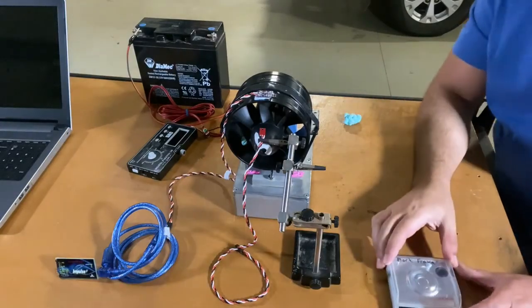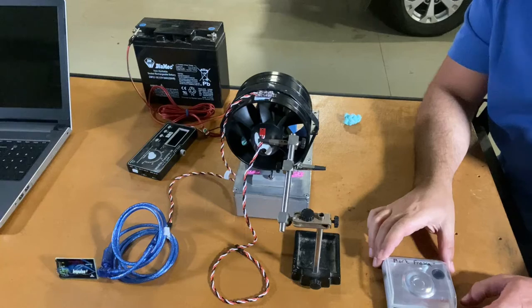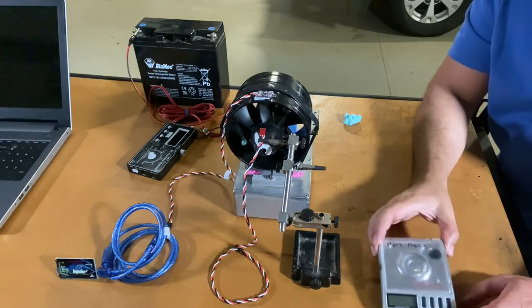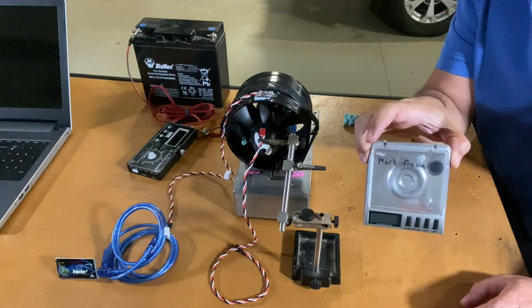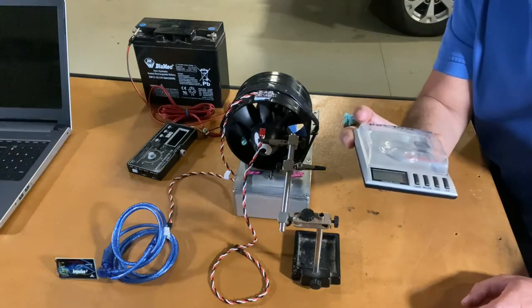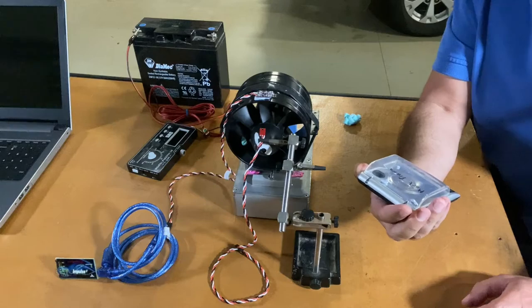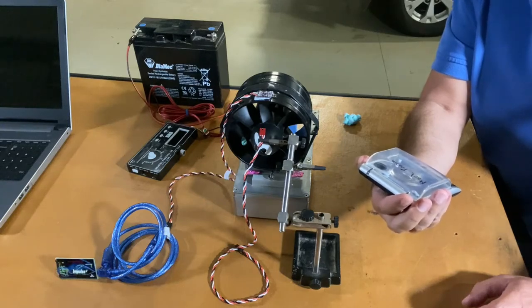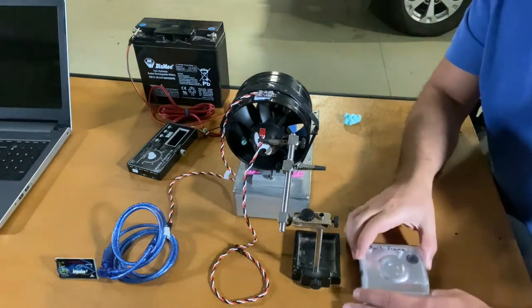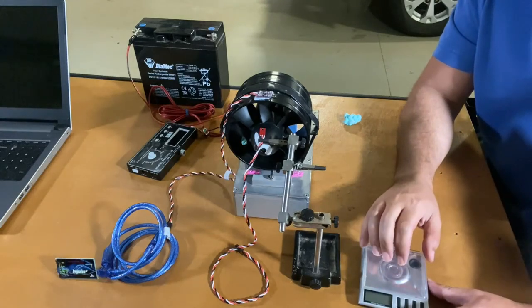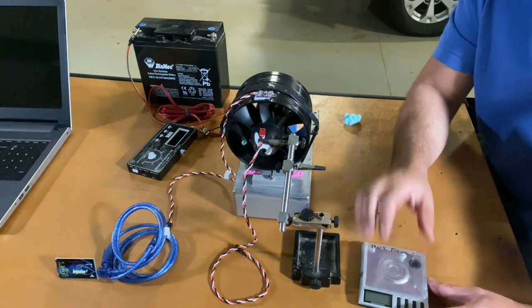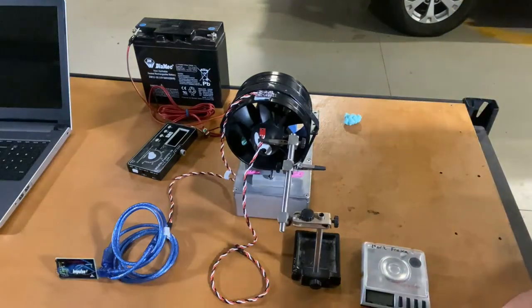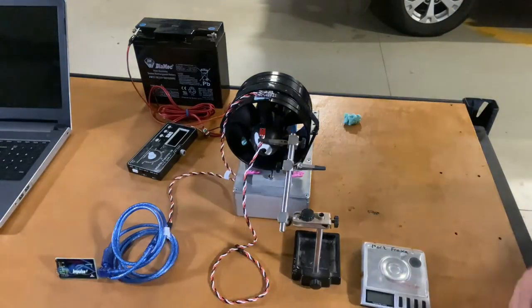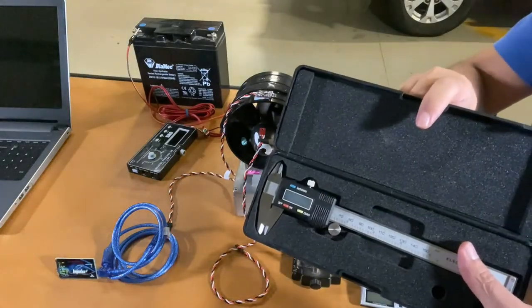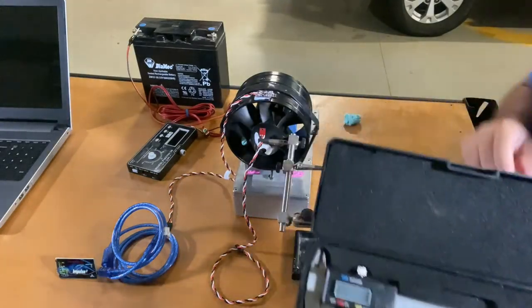Now you will need some other items, guys, to carry out the balance for the single plane method. The first item is actually a set of scales. Now these are jeweler's scales. They're very sensitive. They go down to, in this case, 0.001 of a gram. Essentially you need that kind of accuracy when you are measuring trial weights or balance weights for EDFs. The other thing you would need is a set of calipers, and that's just measuring the diameter of the hub, and I'll show you the purpose behind that later.